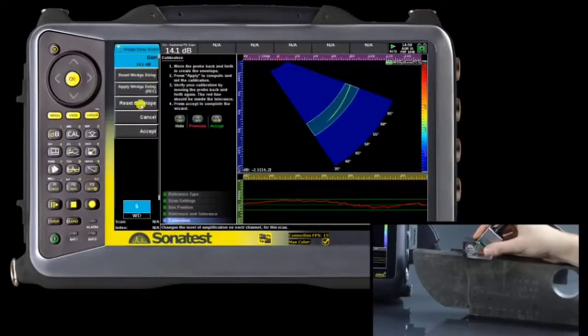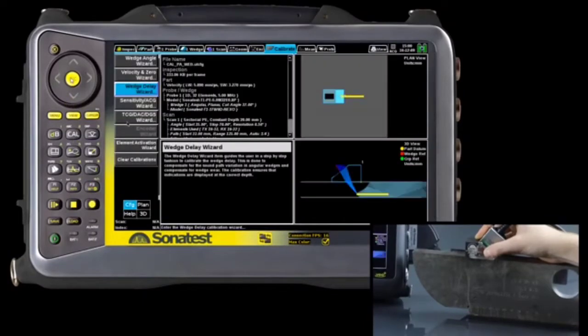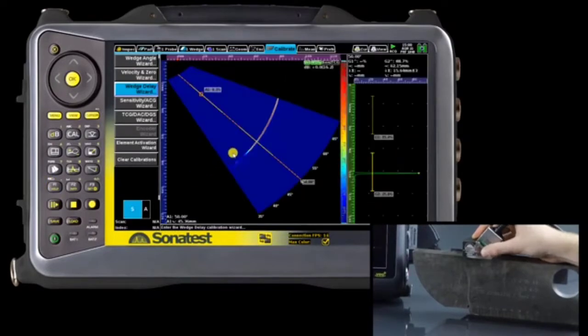We can now see that our reference is at 100 mil and that the tolerance by default is 2 mil. If you're unsatisfied with your wedge delay correction, it is possible to remove the envelope. Once the reference swept, the wedge delay correction can be applied. When the signal is within the required tolerance, we press F3 and accept the calibration. We can now see that the reflector is at 100 mil for all angles and that the wedge delay calibration indicator status is green.